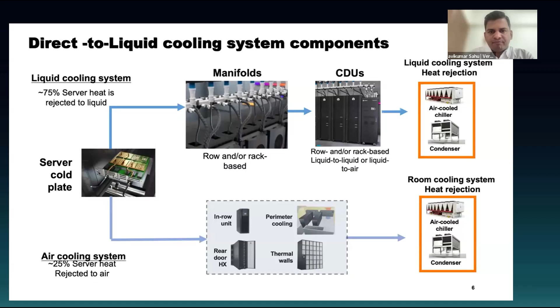So how does this DCLC look? This is a row-based configuration where one CDU can serve multiple racks. You can see the primary fluid network, which is nothing but your facilities water, maybe either from chillers or dry coolers, and the secondary fluid network, which is your technical fluid, or glycol, which is going into the cold plates.